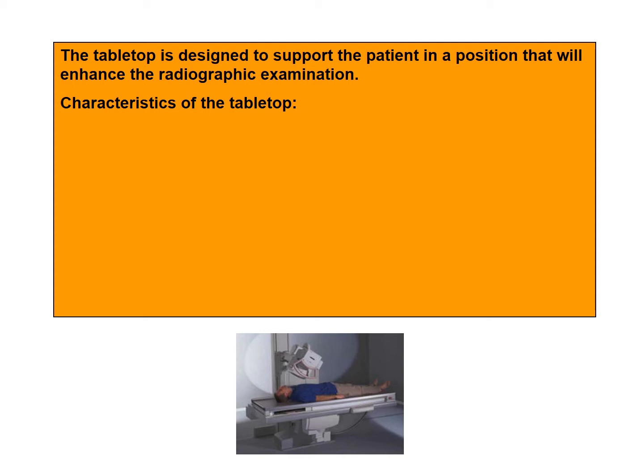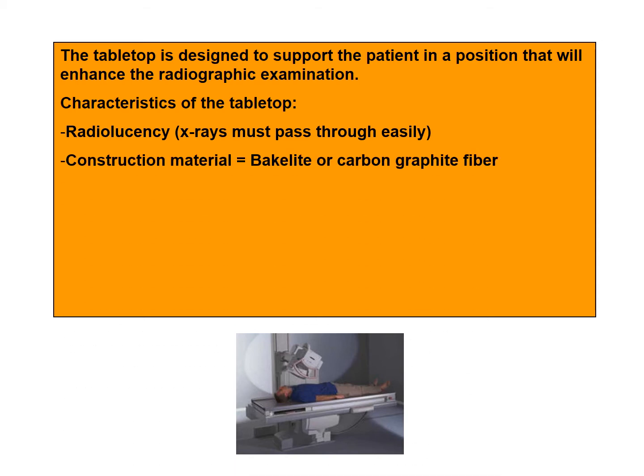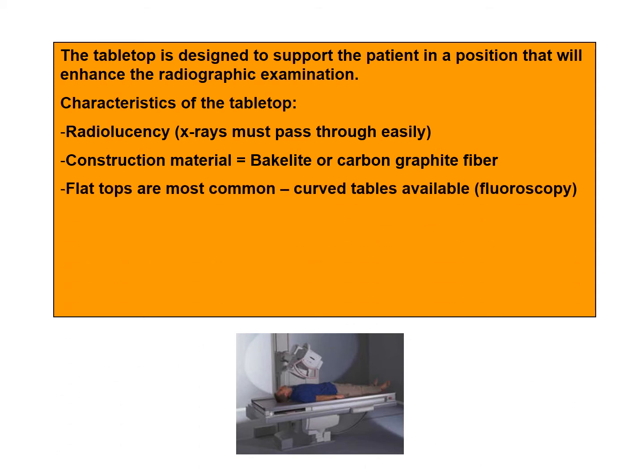First of all, the tabletop. The tabletop is designed to support the patient in a position that will enhance the radiographic examination. Some characteristics: the tabletop has to be radiolucent, so X-rays have to pass through it easily. It's usually made out of bakelite or carbon graphite fiber, which is lightweight, radiolucent, but very strong. Most of your tabletops are flat. Some of your fluoroscopy tables have a curved table to them.